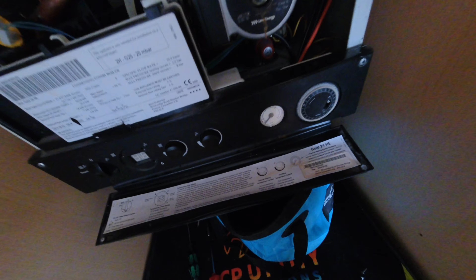Right, boiler is drained out, so we're at 0 bar pressure. Taking the fuse out of there, and surprise, surprise, it's a 13 amp fuse, so we'll be changing that to a 3 amp. Got my gauge on for recharging the expansion vessel, it's at 0.35 bar, so let's top that up to 1 bar.